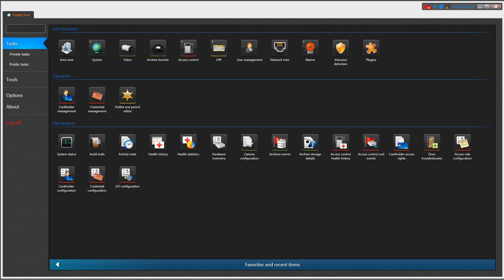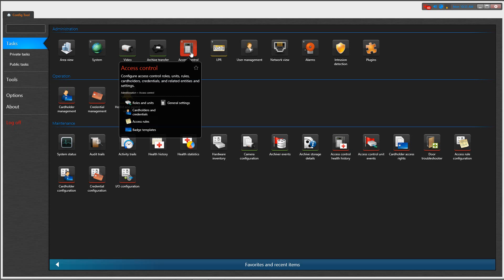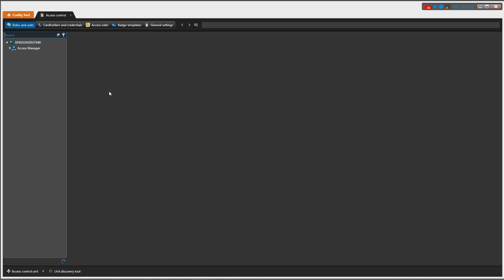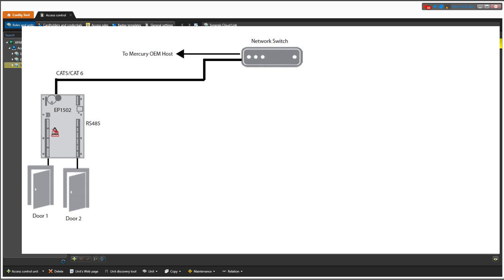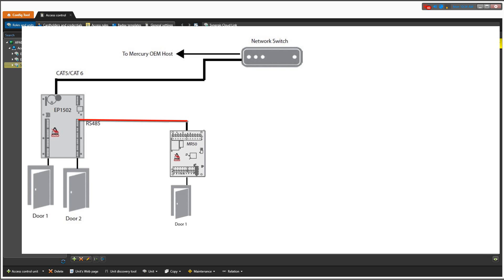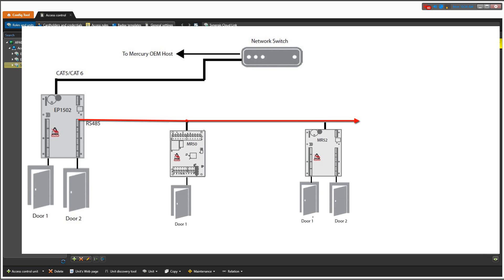I will now demonstrate how to add an MR50 and MR52 in Security Center. For this process config tool will be required. We already have an EP1502 controller added to our Synergis cloudlink. The MR50 connects to the EP1502 through the RS485, and then it daisy chains to the MR52 panel through the same bus. MR50 is addressed 0, and the MR52 is addressed 1.